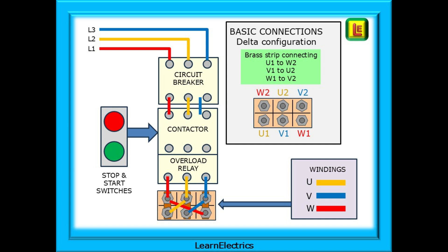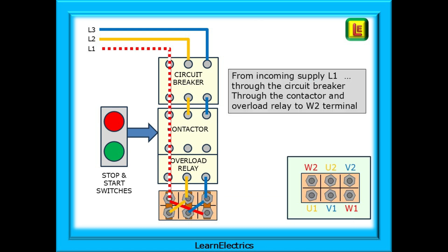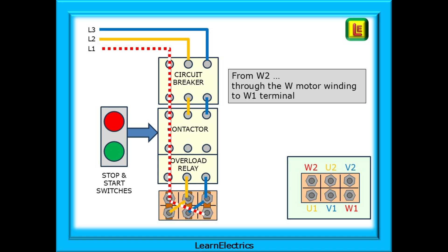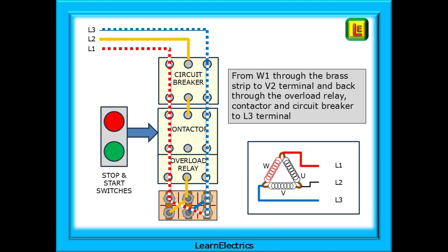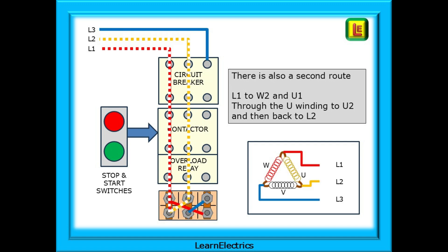Shown here are the connections for a delta configuration. Three brass strips are arranged across the block connecting U1 to W2, V1 to U2, and W1 to V2. Let's follow the route of the electric from the circuit breaker at L1 and all the way back to L3. From the incoming supply at L1, current passes through the circuit breaker, then through the contactor and the overload relay to the W2 terminal on the motor block. From W2, the wiring goes into the motor through the W motor winding and then to the W1 terminal. From W1 through the brass strip to the V2 terminal and then back through the overload relay, the contactor, and the circuit breaker to the L3 terminal at the distribution board. There is also a second route: L1 to W2 and along the brass strip to U1, through the U winding to U2, and then back to L2.